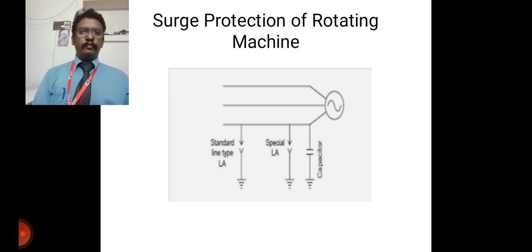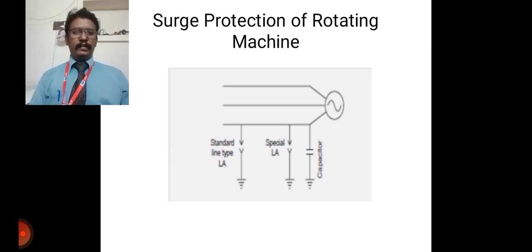To protect the major insulation, a special lightning arrester has to be connected at the terminals of the machine, and to protect the minor insulation, a condenser of suitable rating has to be connected at the terminals of the machine. So these are some of the techniques we can adopt to protect our devices against overvoltages.